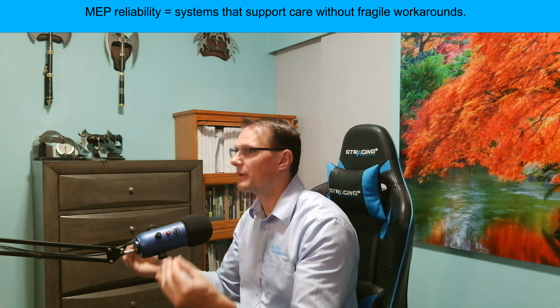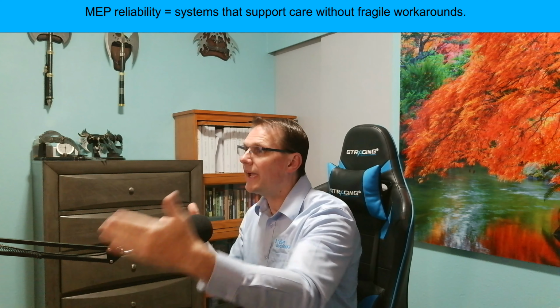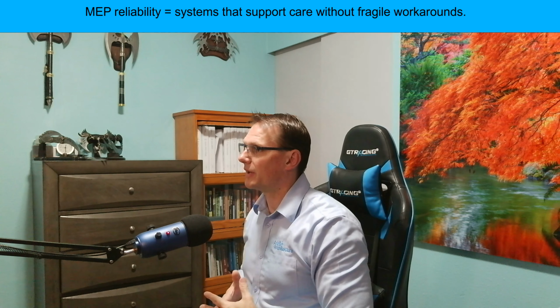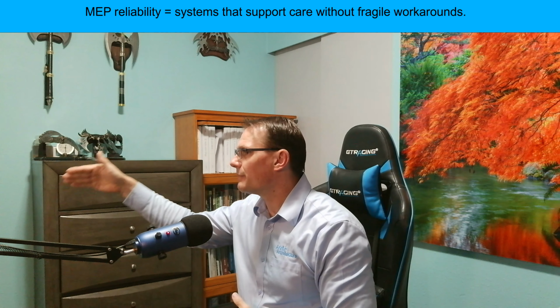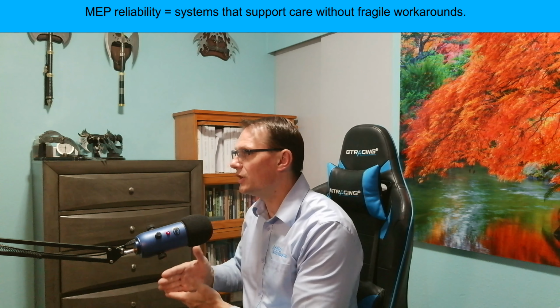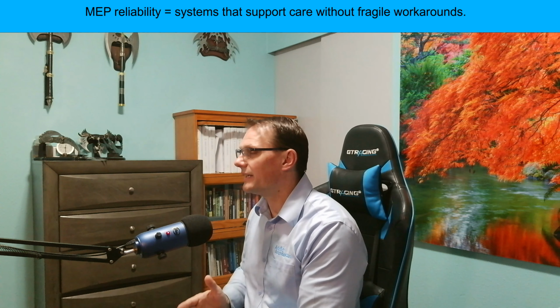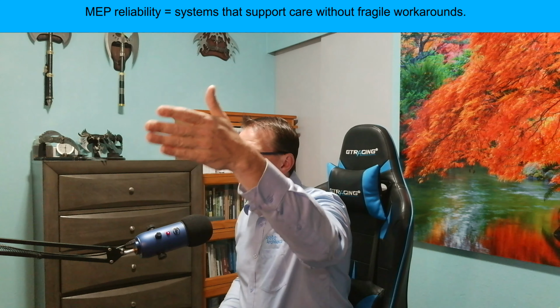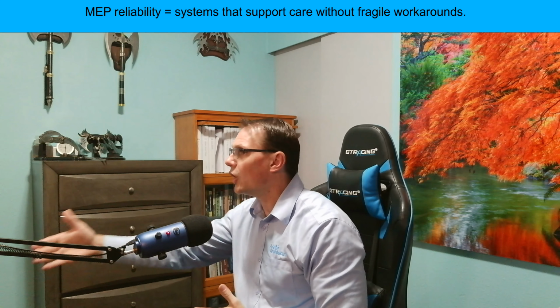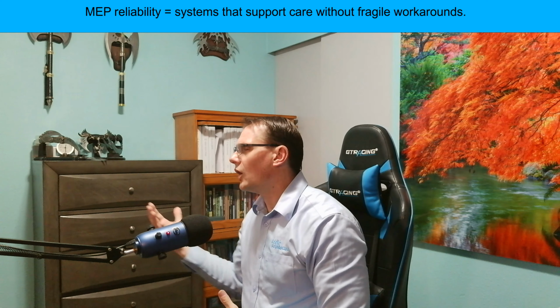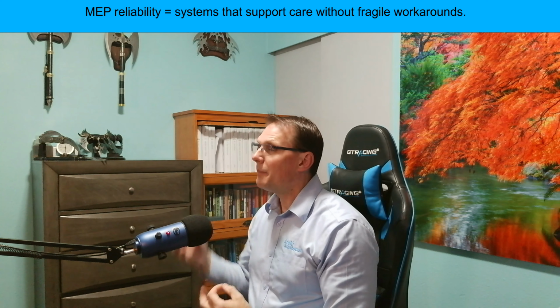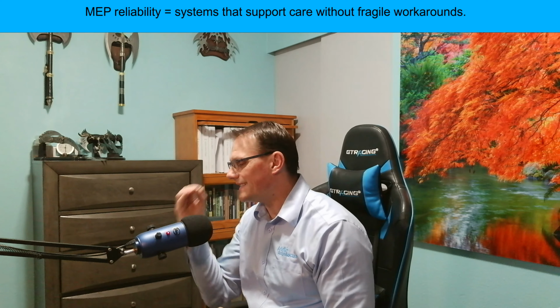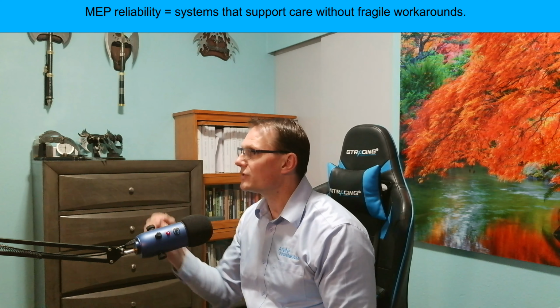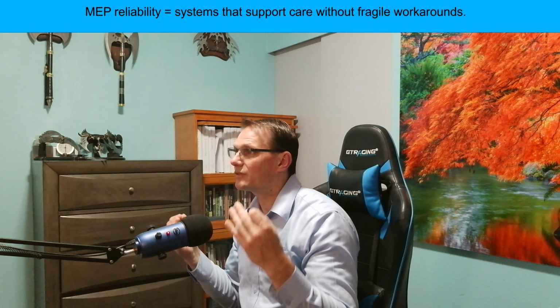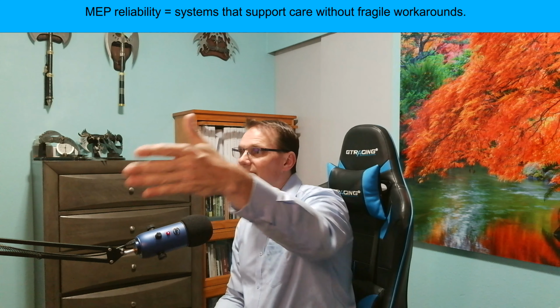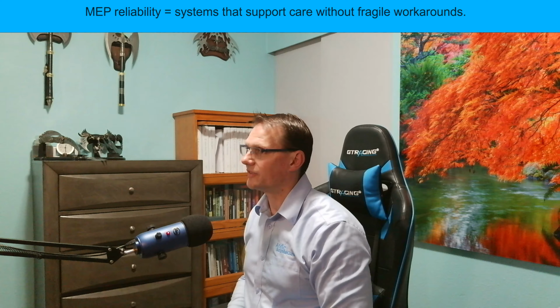Redundancy means backup capacity or an alternate way to keep a critical function operating. The right level depends on the care model, acuity, resident or patient risk, staff model, existing building conditions, code requirements, and owner tolerance for downtime. But the decision should be intentional. The dangerous version is when reliability is reduced by accident because the team only looked at first costs.